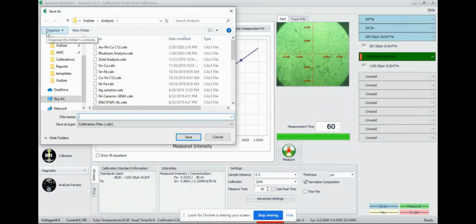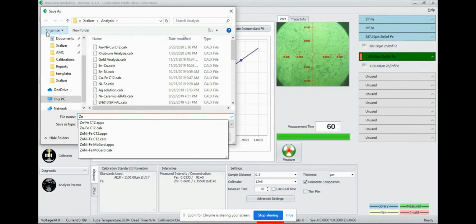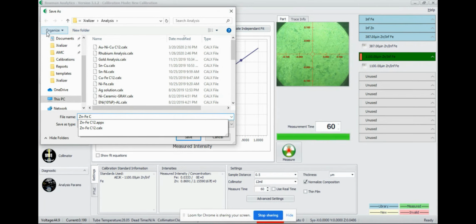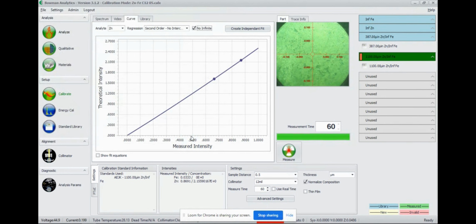And since it's a new one, it's going to ask us for a name. I like to be fairly clear on my name and put in what my coating is, my substrate. I like to put in the collimator and also my sample distance. This becomes really important when you have multiple either collimators or measuring distances, so you know that the application you're making has been calibrated with the right settings. This way it's really easy to know what your calibration settings were without having to go in and check the calibration file, and that becomes really important when we're building our application. And now we save, and at this point we are done with the calibration.